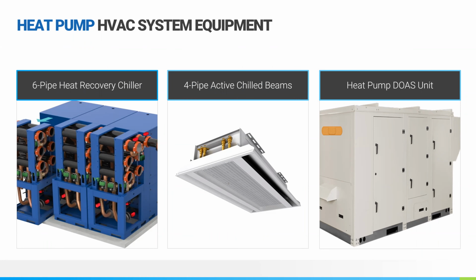Your ventilation air from the unit on the far right there is called an outside air processing unit. The ventilation air, this is big in the COVID world. Your outside ventilation air is pre-processed by that unit, taken through MERV 13 filtration, and then entered into the space at a predetermined rate set by the American Society of Heating, Refrigerating and Air Conditioning Engineers. So the outside air comes in through that unit, and then that air is either cooled or heated using the chilled water, hot water plant that you'll see there on your left.